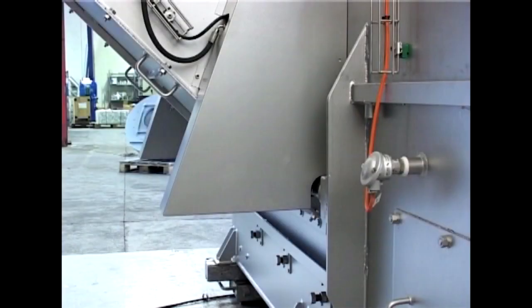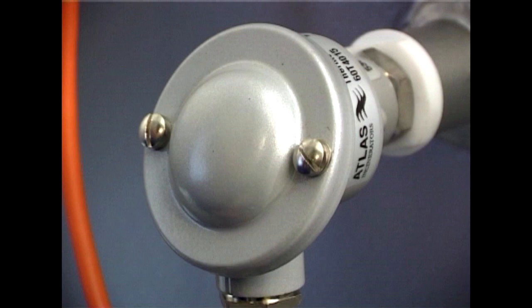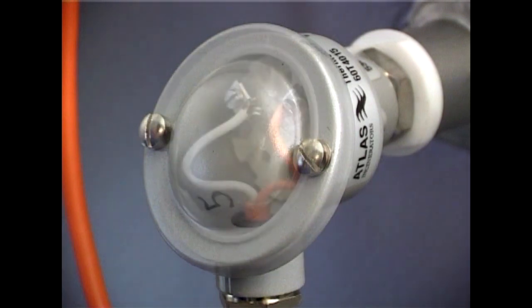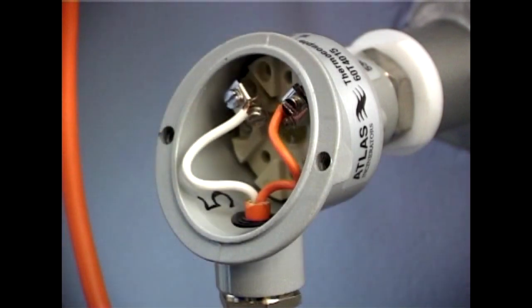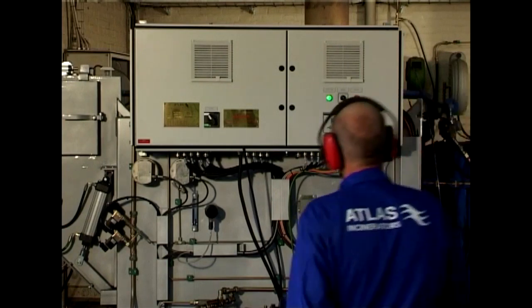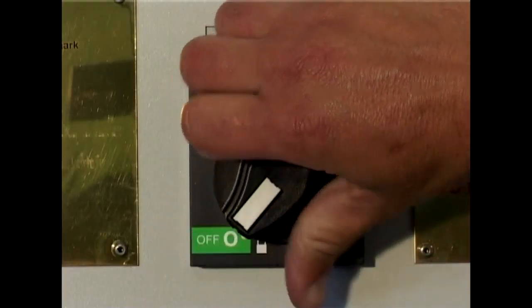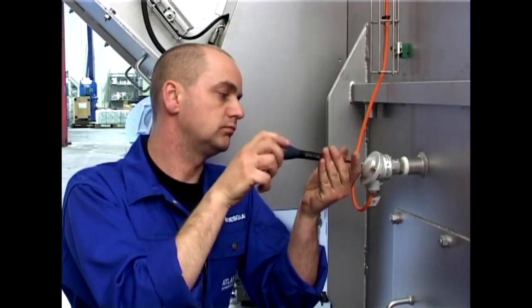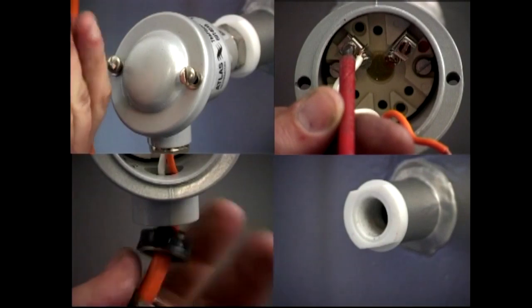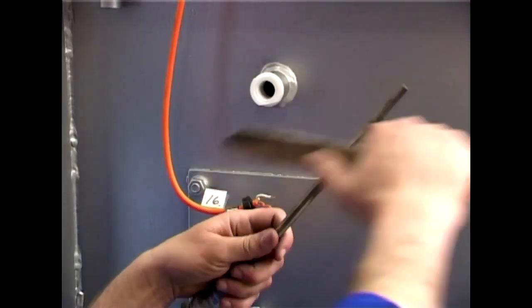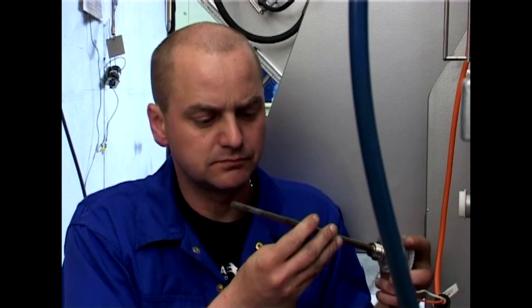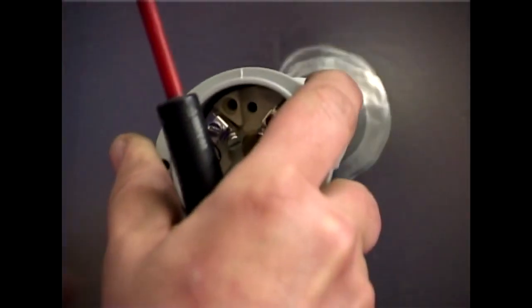The thermocouples are installed directly into the combustion chambers and in the chimney. This position exposes them to strong heat, which can potentially damage them over time. Therefore, the thermocouples should be checked frequently, and this can be done in the following manner. Begin by switching off the incinerator. Then dismantle the thermocouples one by one. Clean each of the thermocouples with a wire brush. At the same time, you should also check them for any mechanical damages like cracks and replace them if necessary. Finally, reinstall the thermocouples.